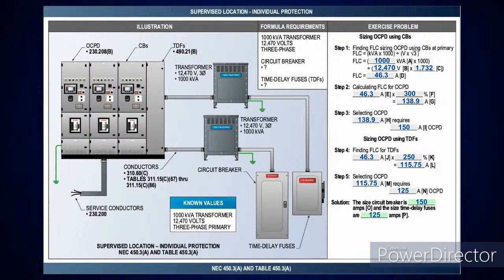In here, we're going to be calculating the overcurrent protection device for the primary only, and we're going to do it for circuit breakers and time delay fuses. Remember when we were talking about this last week, I said you want to go look at table 450.3(A), and this one is a supervised location. As you look at the table in the left-hand column, you're going to come down to where it says supervised. And as you look at this problem, we have a transformer.